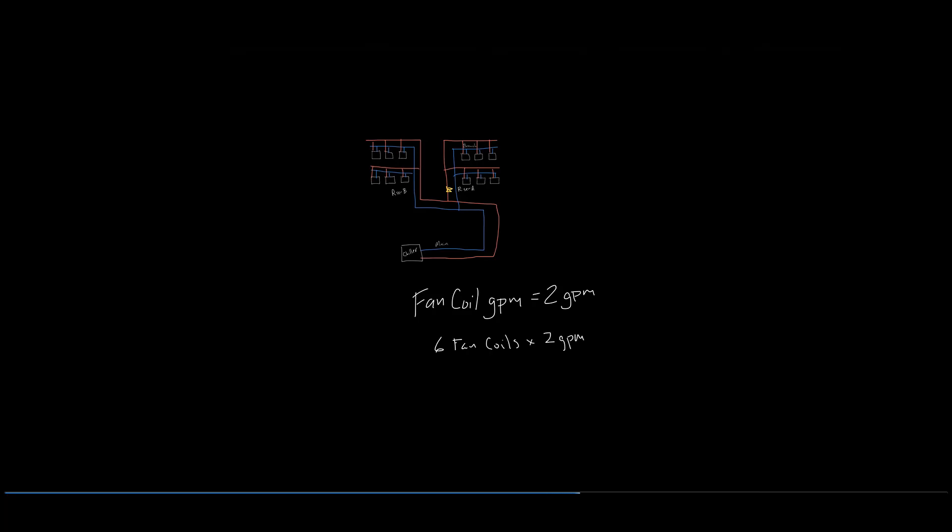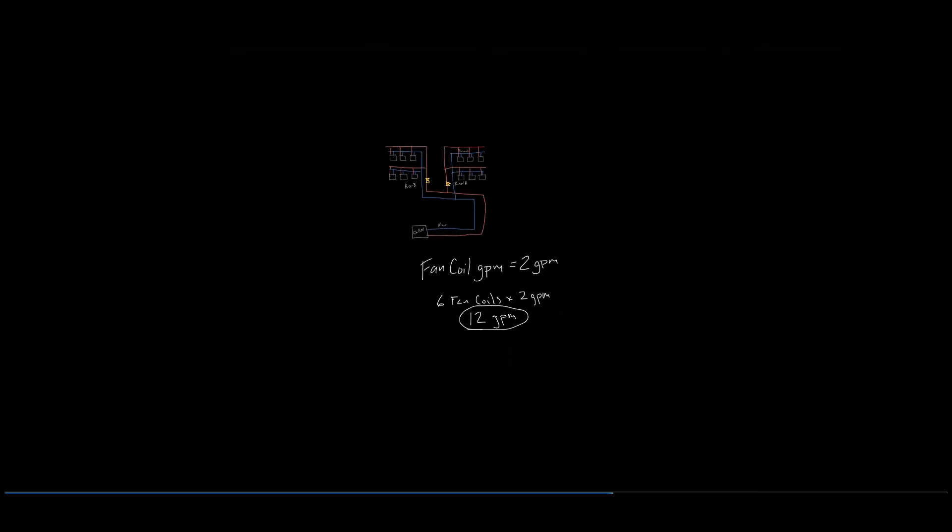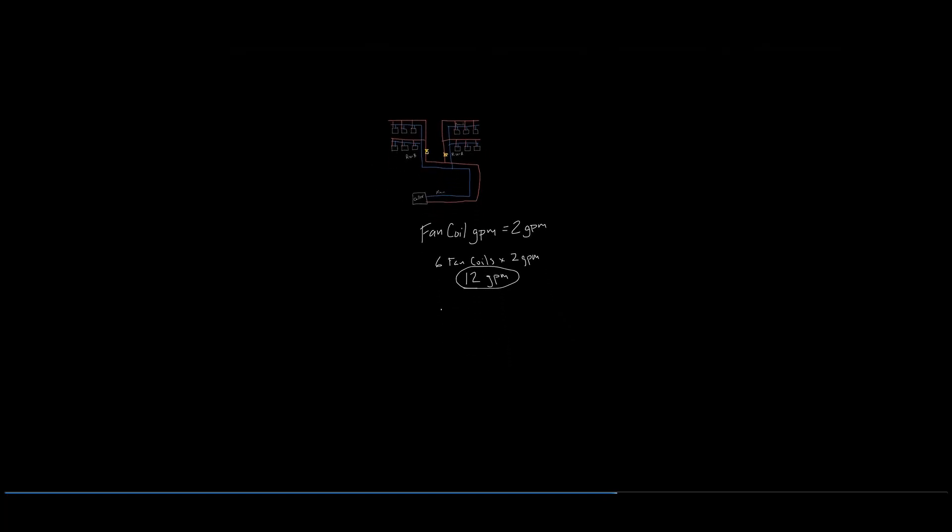Starting with riser A, it has six fan coils that require a two GPM flow rate to meet the design requirements, and riser B also has six fan coils that require two GPM per design. The total design flow per riser will be six fan coils at two GPM equaling 12 GPM.